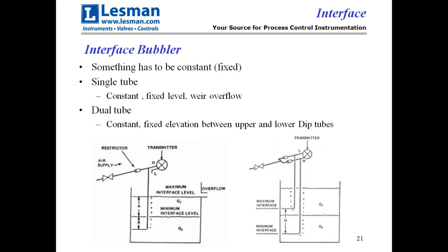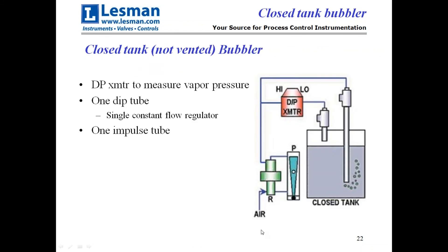In a closed tank — not a vented tank — you can use a bubbler with a DP transmitter and only one bubbler tube. Air comes in, gets constant-flow regulated, creates the bubbles at the bottom. The second tube is just an impulse tube in the vapor space up top, running to the low side of the differential pressure transmitter. This subtracts the vapor pressure from the combined vapor pressure plus liquid head, to get just the liquid level — one impulse tube, one constant flow regulator, but you use a DP transmitter.